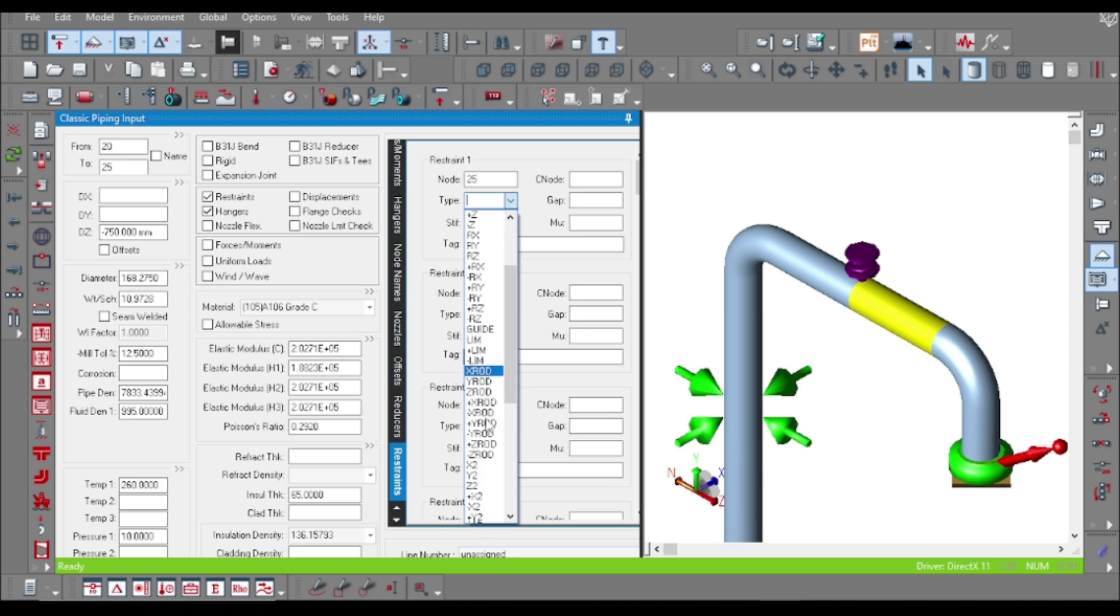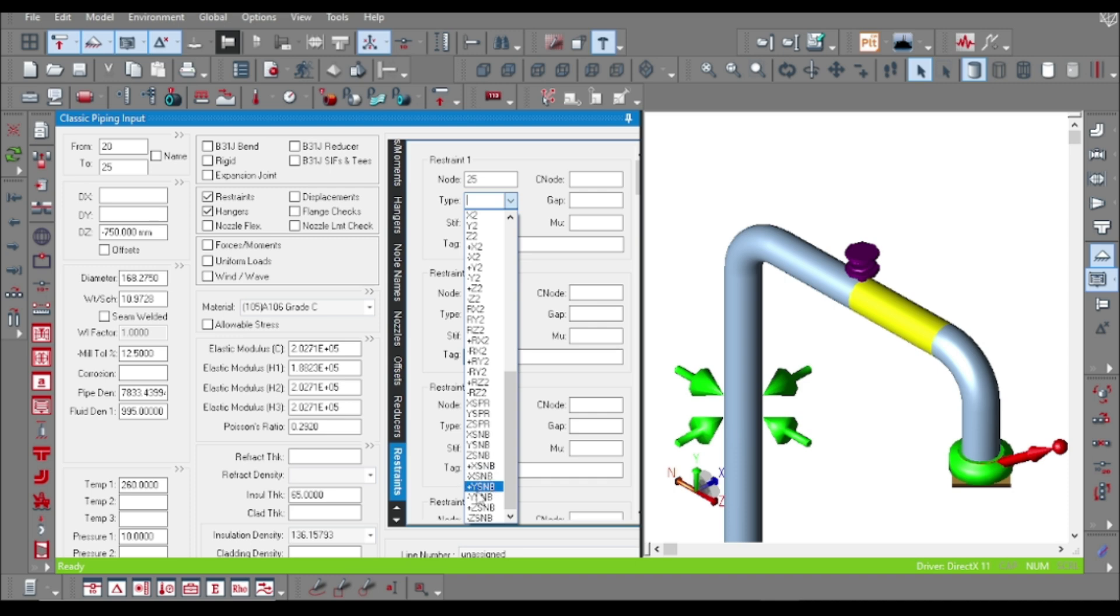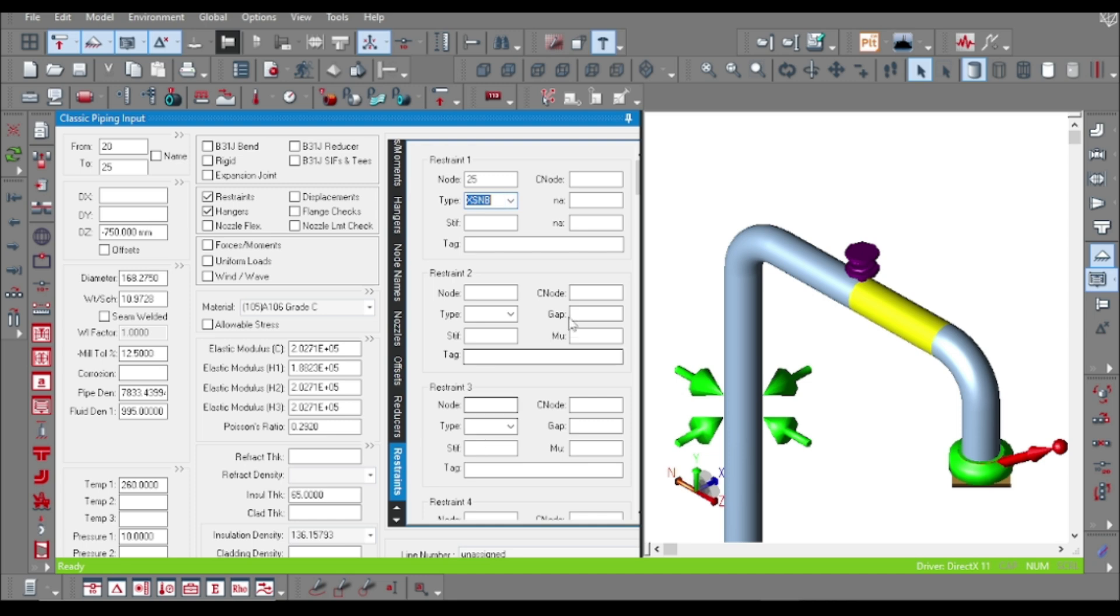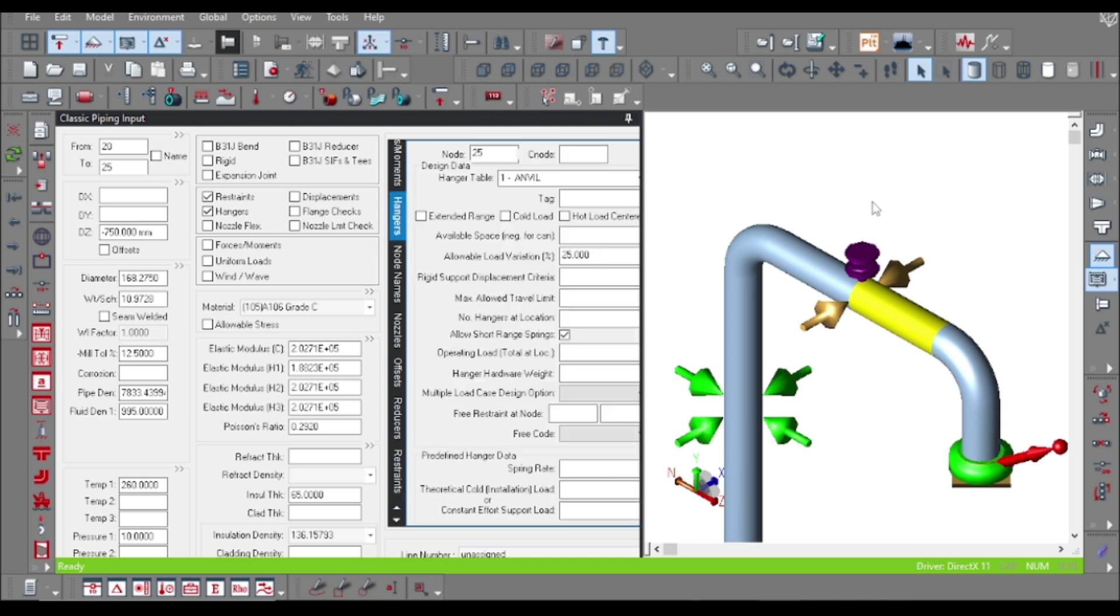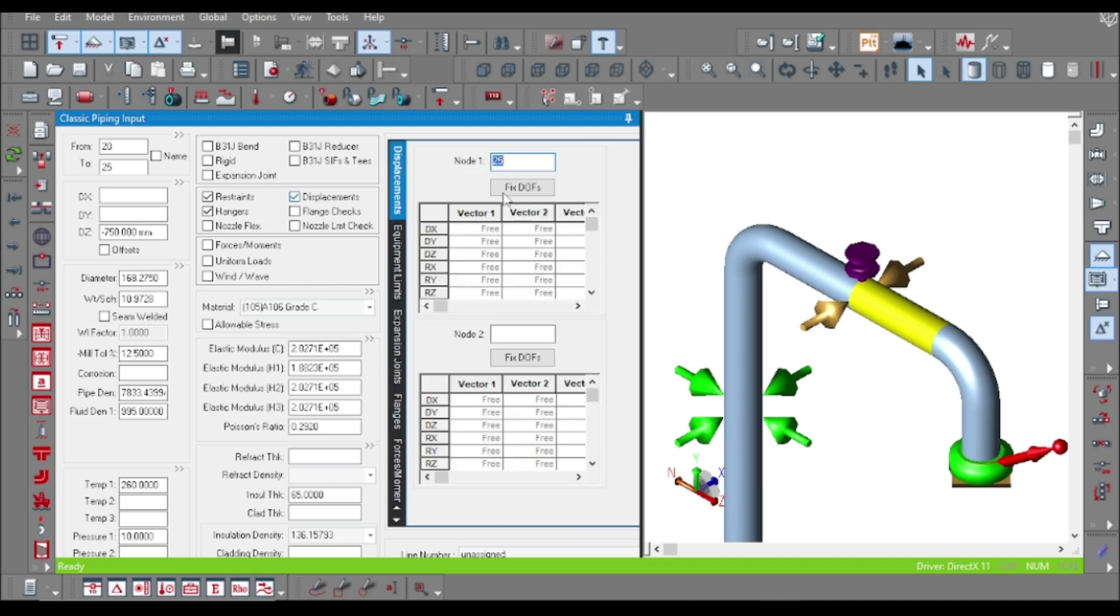Now to provide snubber support, just click on the restraint. The support type will be the last options: X snubber, Y snubber, Z snubber, and rigid snubber support. Suppose I want to put an X snubber, so it would appear as a guide. Now we have to provide a connecting node. Suppose I am putting node 26, and here just click on the displacement.